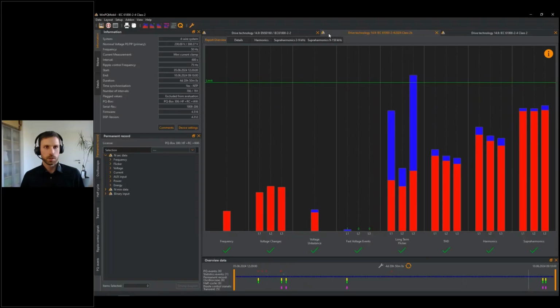A few years ago, we changed the philosophy, because in the past you had to tell the PQ-Box before the recording which standard to apply. So before the measurement, you had to choose whether you want to go with -2-4 for industrial applications or -2-2 for public grids, for example. And changing the method afterwards was not possible. So if you got the wrong standard, the wrong settings, it was not possible in the past. We changed this, and now you can change your evaluation method afterwards as you want.